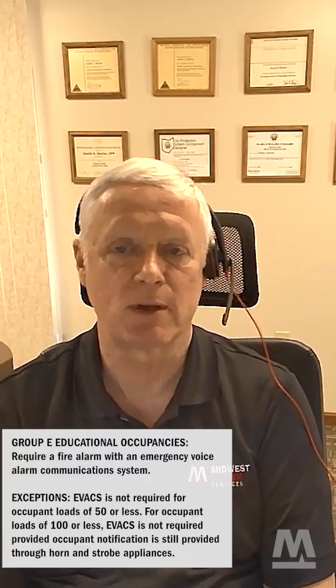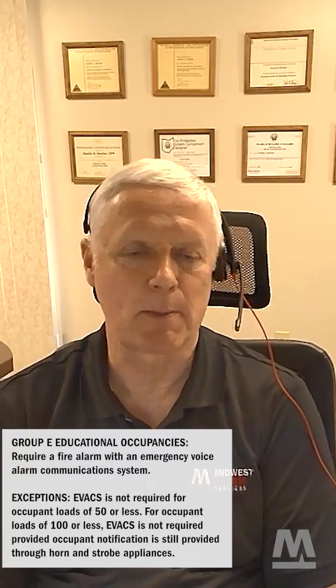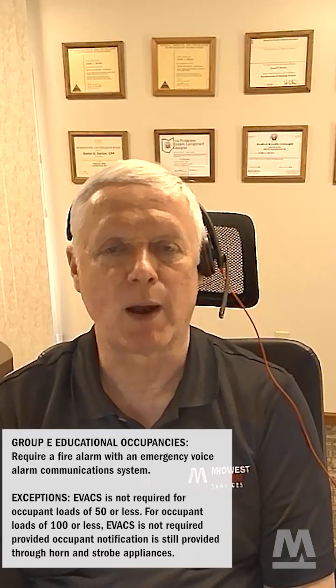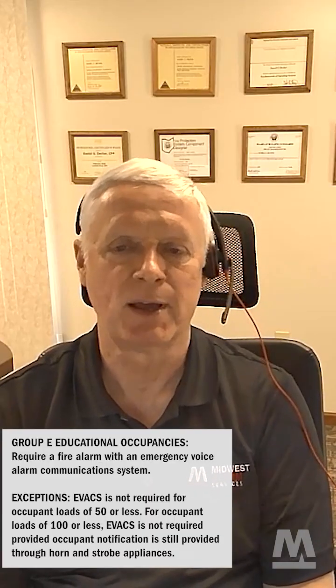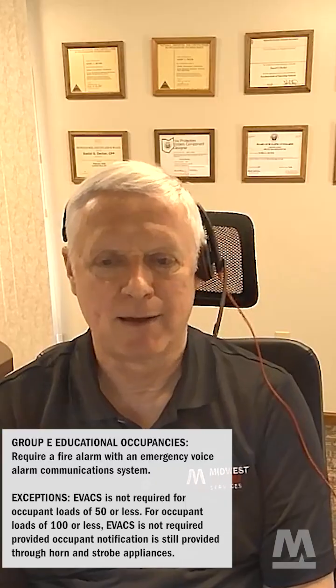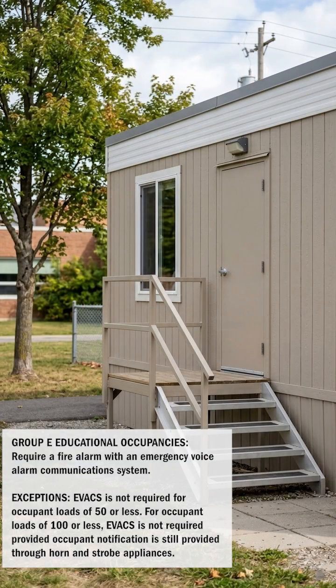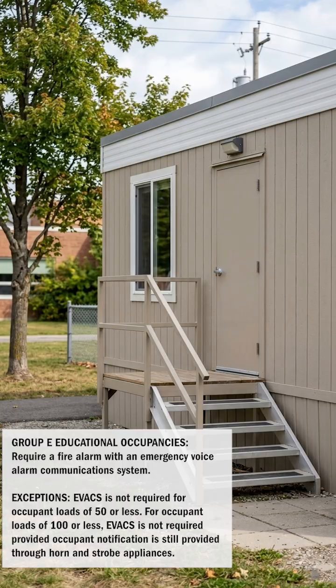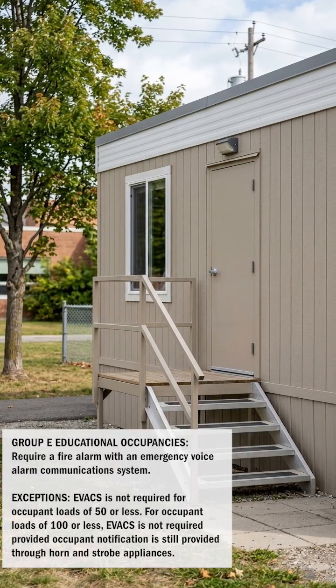Group E covers schools and educational facilities. I know that these have some specific requirements around voice evacuation, similarly to assembly occupancies. What's the story there? Yes, Group E occupancies under the International Building Code require a fire alarm system with an emergency voice alarm communication system. The exceptions are pretty limited. Evacs is not required for occupant loads of 50 or less. So that would probably be your portable trailers that they bring in for a class or two. 50 is a pretty small number in terms of a school.